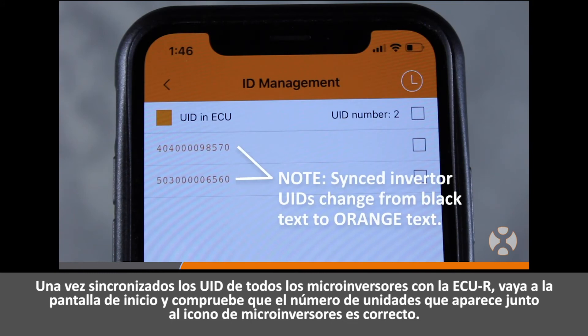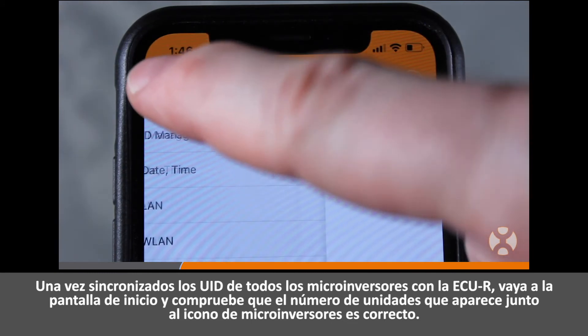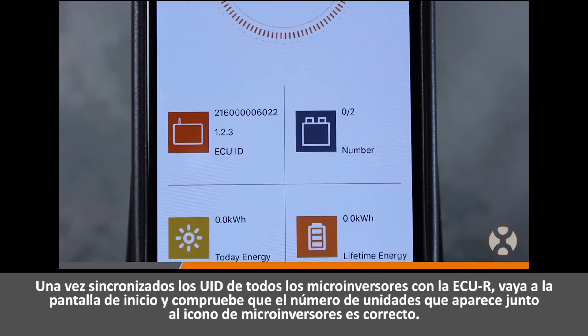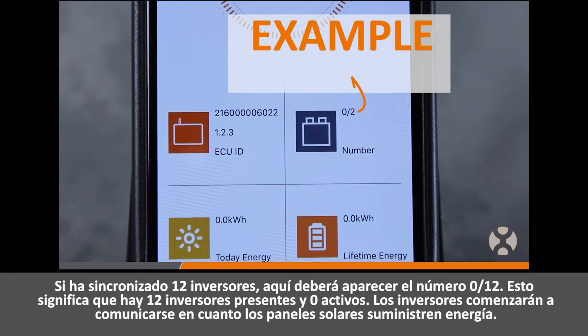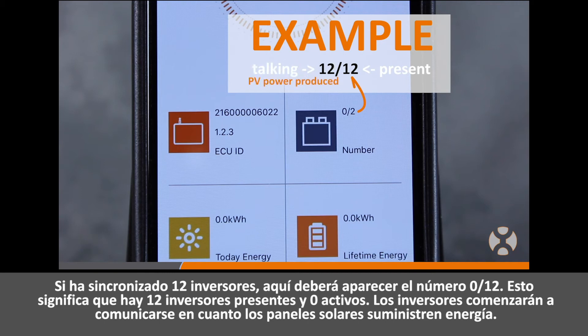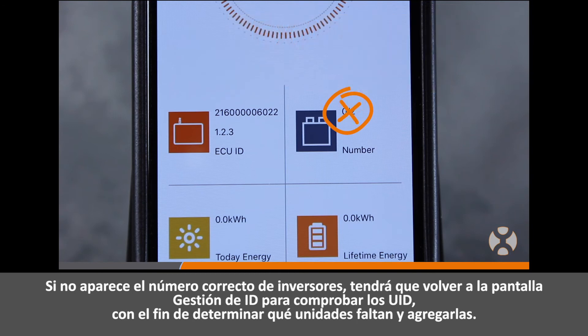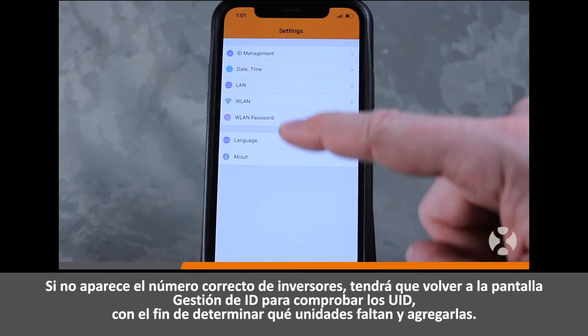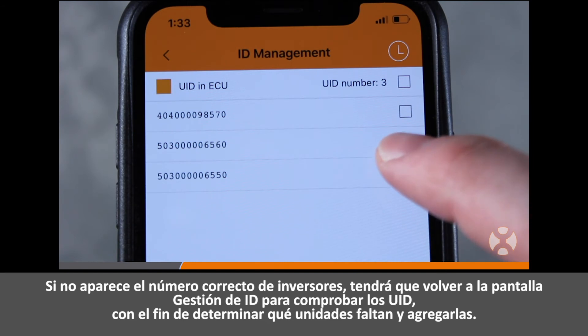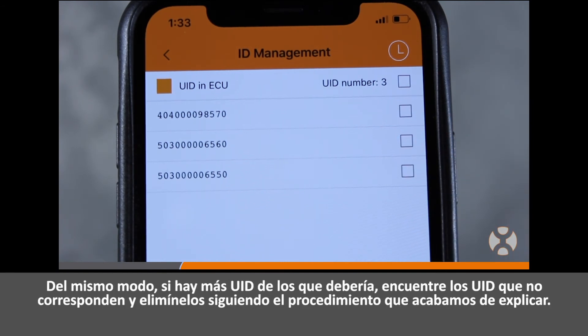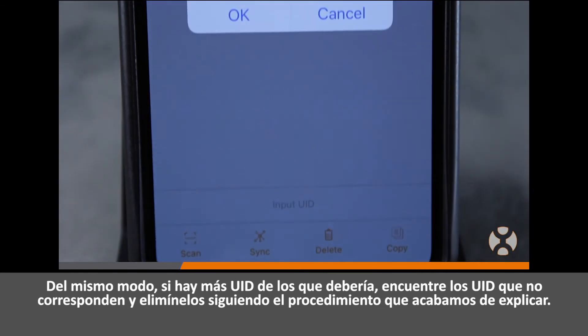After all the microinverter UIDs are synced to the ECU-R, go to the home screen and verify the number of microinverter units displayed next to the microinverter icon is correct. For example, if you synced 12 inverters, the display should show 0 over 12 — meaning 12 inverters are present with 0 currently communicating. The inverters will begin communicating once power is supplied by the solar panels. If the correct number is not displayed, return to the ID Management screen to verify which units are missing, add them, or remove any UIDs that do not belong.